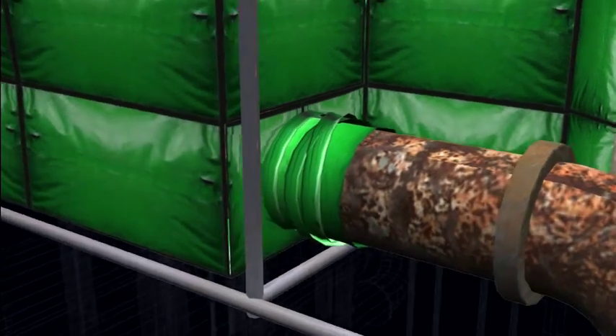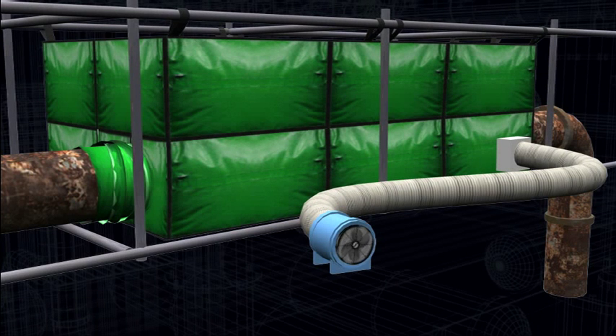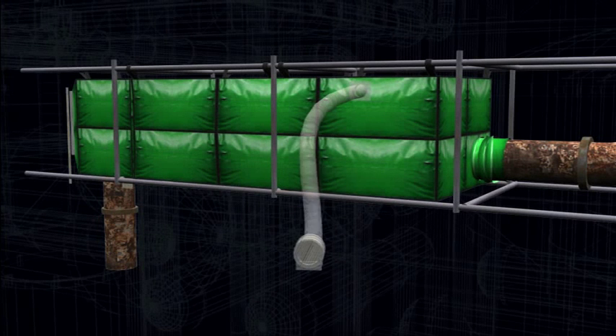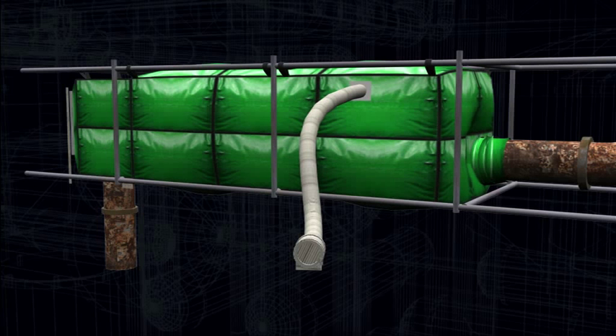Finally, the inlet and outlet systems are installed to allow clean air to be drawn from a safe location, and any gases and fumes from the hot work to be extracted, either generally or locally, through further ducting to a safe area. The clean air driven into the system creates a positive pressure environment, which is monitored constantly to ensure there is no detrimental effect on the welding processes.